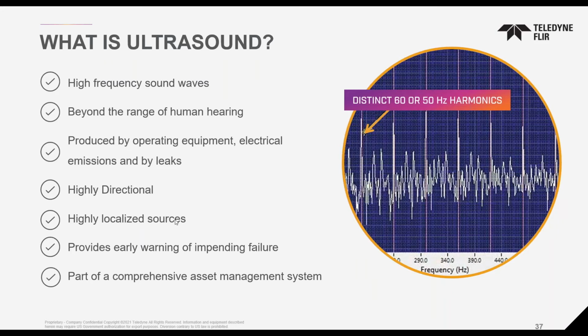It's highly directional, so wherever that sound is coming from, it travels in a certain pattern from highly localized sources. For example, if you have a compressed air leak, it's coming from that single source. The best part is it provides early warning of impending failure—when you have increased ultrasonic activity, you know you might have impending failure or a leak that could otherwise be fixed.